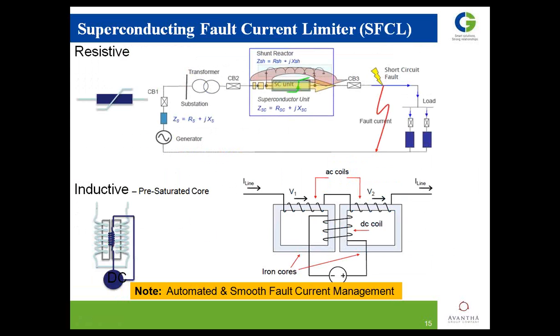A couple of techniques are there: the conventional fault current limiter and the non-conventional fault current limiter, with the non-conventional one specifically toward the superconducting type, in resistive and inductive forms. The resistive one is more popular today, mostly in series, and people add a shunt reactor here to enhance the capacity of the fault current limiter and try to manage or meet that fault current for the utilities. If it is a high voltage or high power case, people prefer the inductive type, like a transformer, and try to manage the fault current by exciting this coil, whatever the problems are.